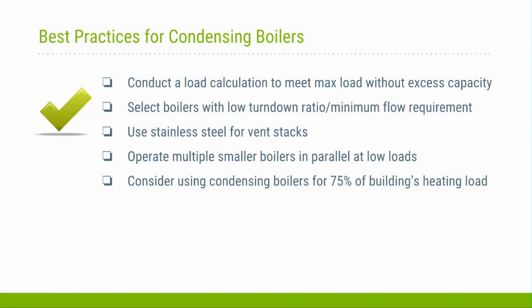This enables you to stage your boilers, a modular approach where you have a few smaller boilers, and you can turn them down low and operate them in parallel, which is the recommended operating strategy. Each manufacturer will have their control strategies, which should be pretty well nailed down, but that's what we saw most effective: a modular design with all of the boilers operating at pretty low turn downs. And then the minimum flow requirement enables you to head towards more of that one piping loop concept where you're not having to flow a lot of water through the boilers at low loads, and again, aids in getting those lower return water temperatures.